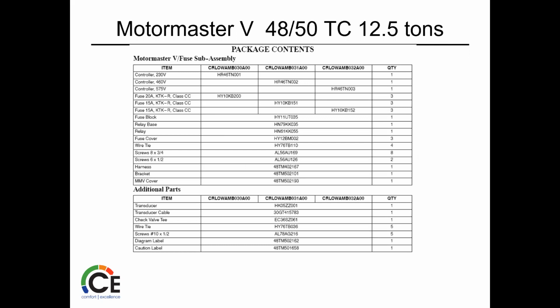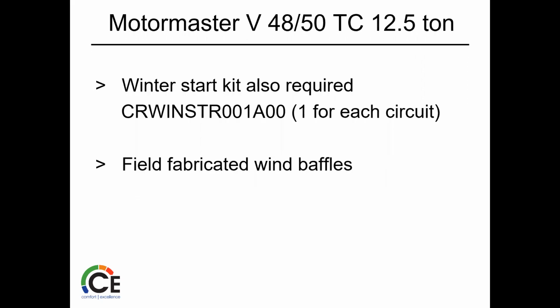So the package has some fuses, fuse block, relay base. You're going to get the covers, transducer, so it's a complete kit when you're buying that. And then again, a winter start kit for each circuit. So if you've got a 2-stage system, you're going to need a winter start kit for both. And again, that's that relay that's just bypassing that low pressure switch so you can continue operation. And then wind baffles.